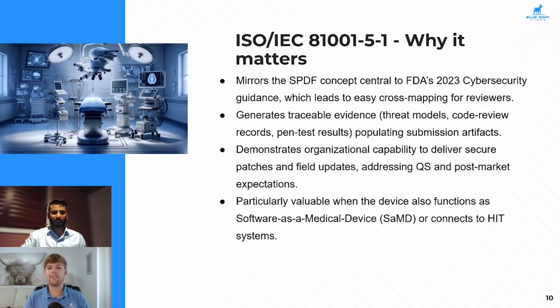I think you bring up a fantastic point about those metrics. So it's a requirement with an FDA submission, any class of submission, to at least provide a plan to collect specific metrics. They want to look at the percentage of vulnerabilities that are remediated as part of a set patch cycle or a set deployment cycle. They want to see what the timeline is from vulnerability identification to remediation availability, as well as remediation availability to deployment in fielded devices. So that's what we're talking about when we're trying to collect these metrics.